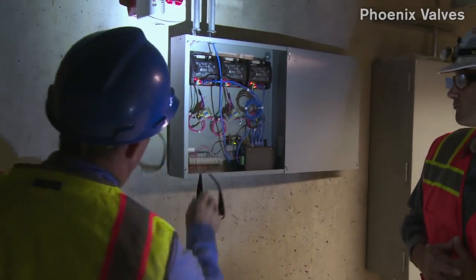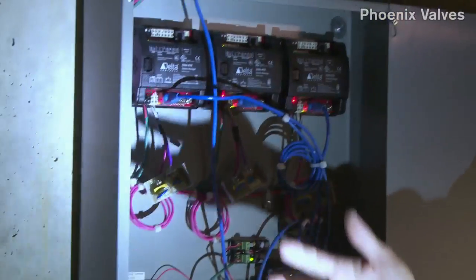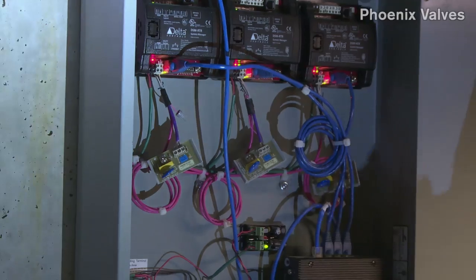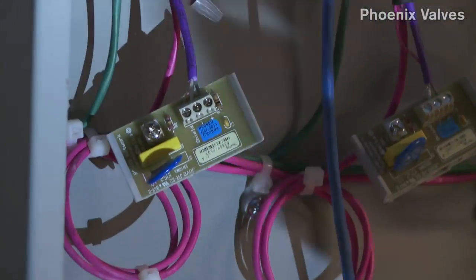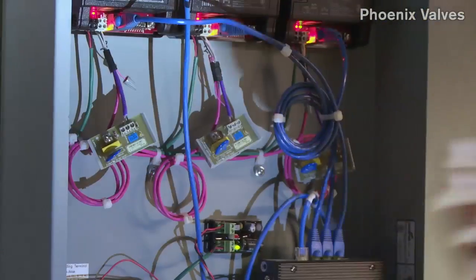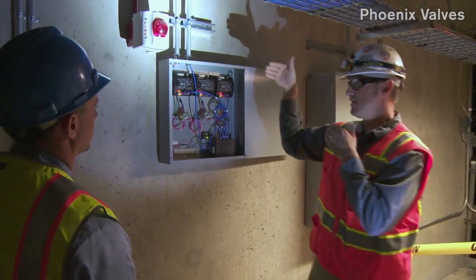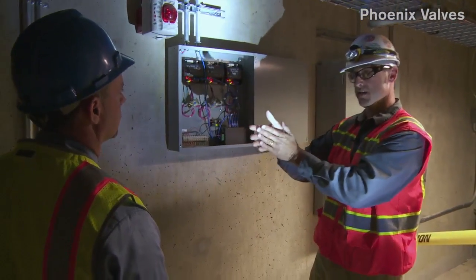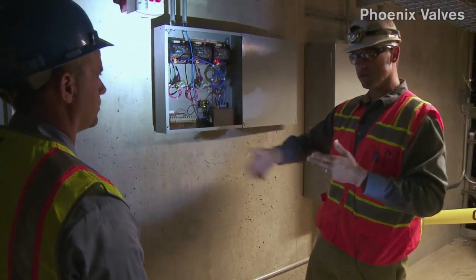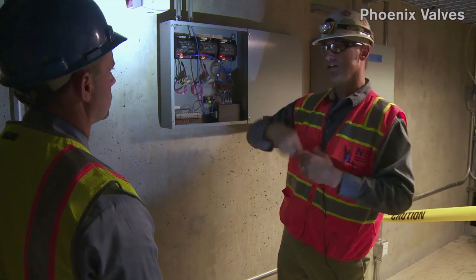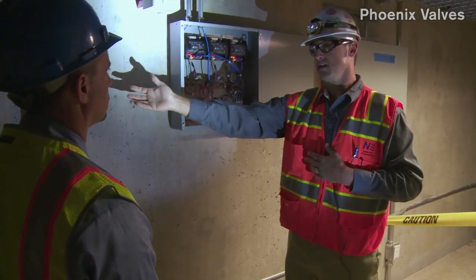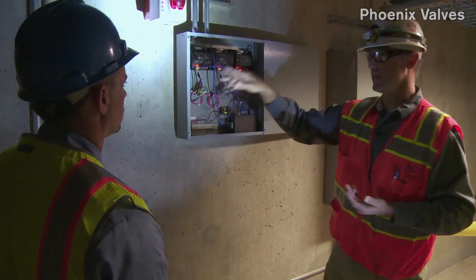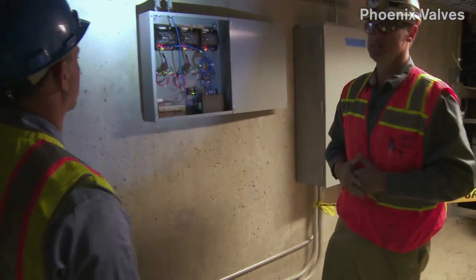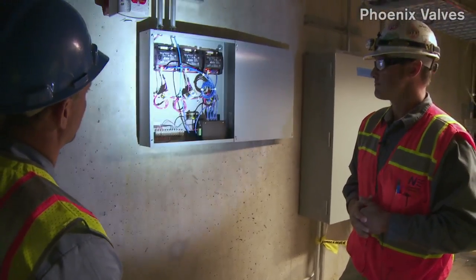And what's that right there? These are the end-of-line terminators. Oh, okay. So when you have so many devices on one comm system, you want an end-of-line. Otherwise, the signal could kind of go out to infinity, and it just slows down the comm. And sometimes you get breaks where a device will pop up, and then it'll go off, it'll pop up, it'll go off. This just completes the circuit, says, hey, this is where I'm ending, just go to here to look and stop. Because it is MSTP, the master-slave token passing, it'll just keep going, and if it doesn't see that, it'll try to send it out, and it'll wait for a little bit, waiting for a response. This here is saying, okay, come to all the devices, stop here, now go back. Stop passing the token, buddy.